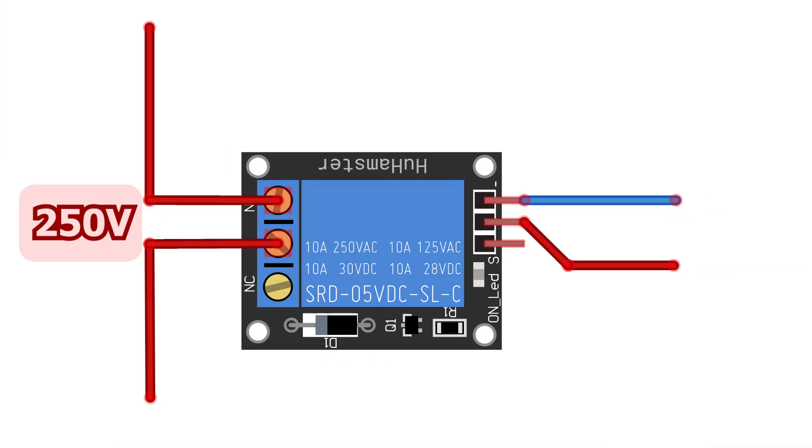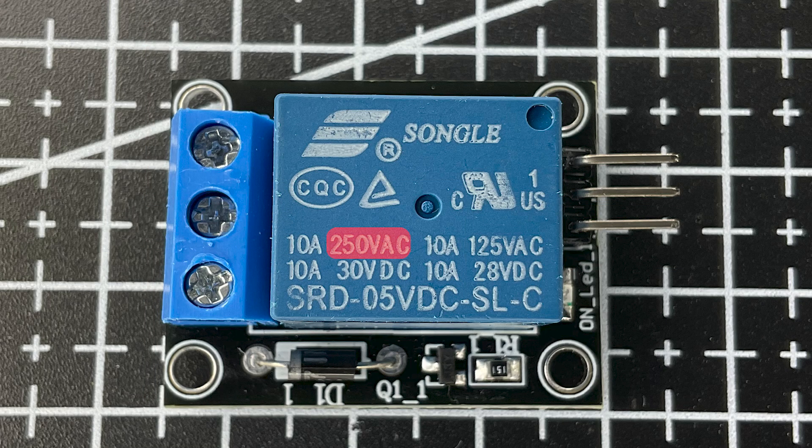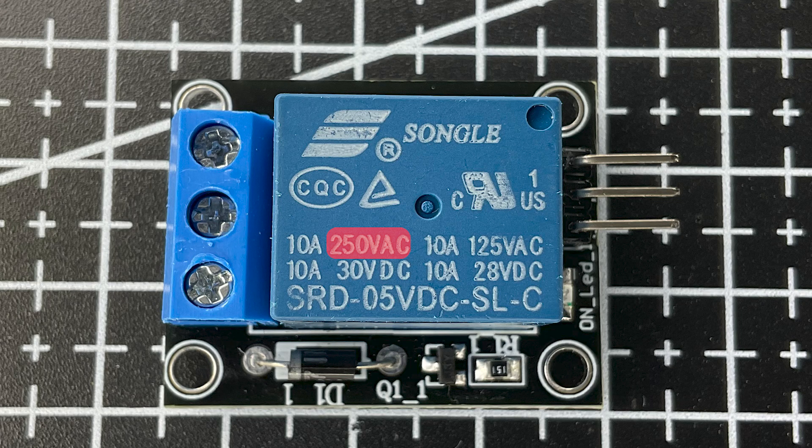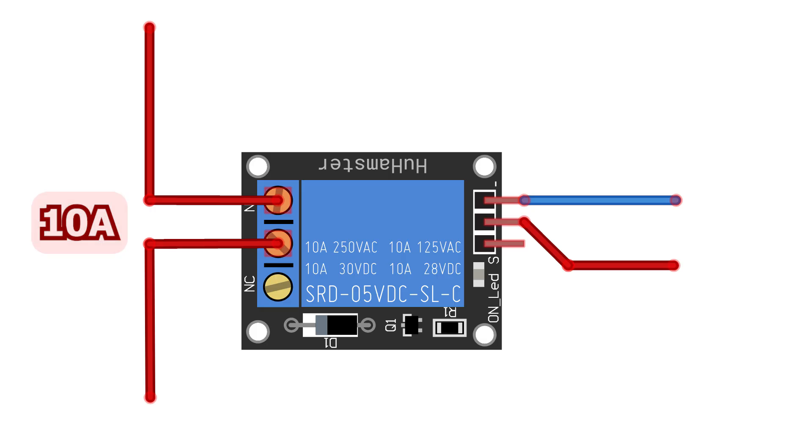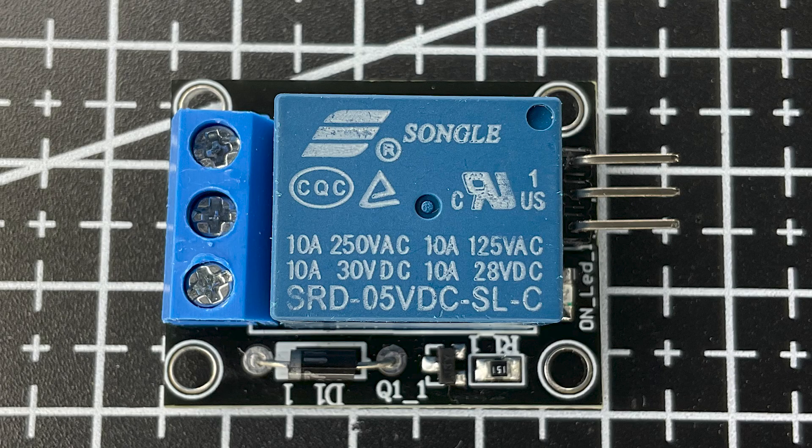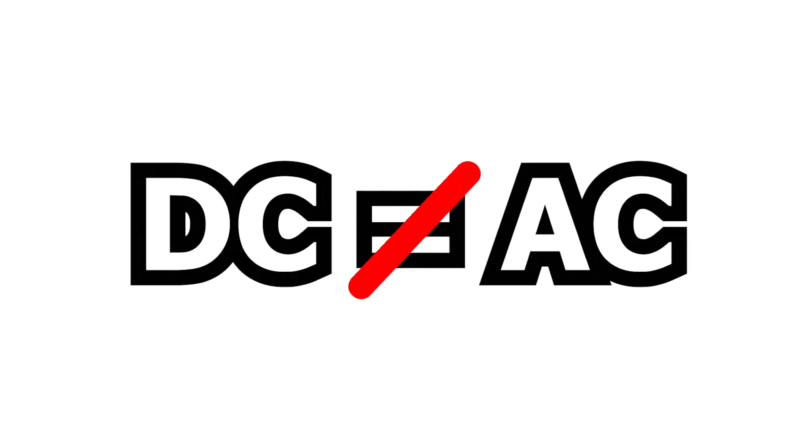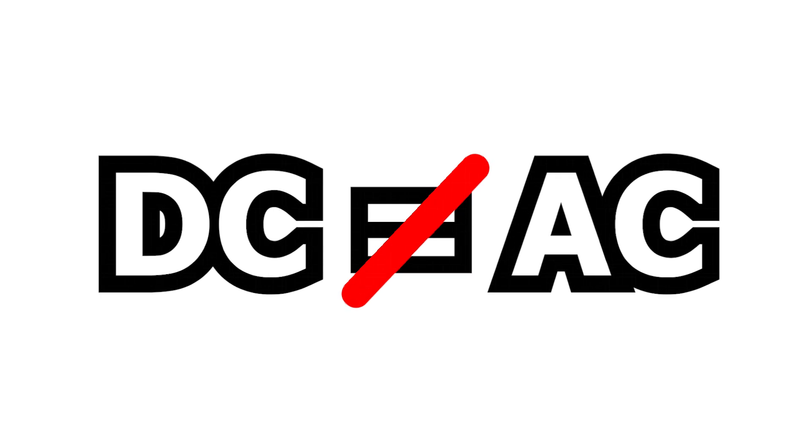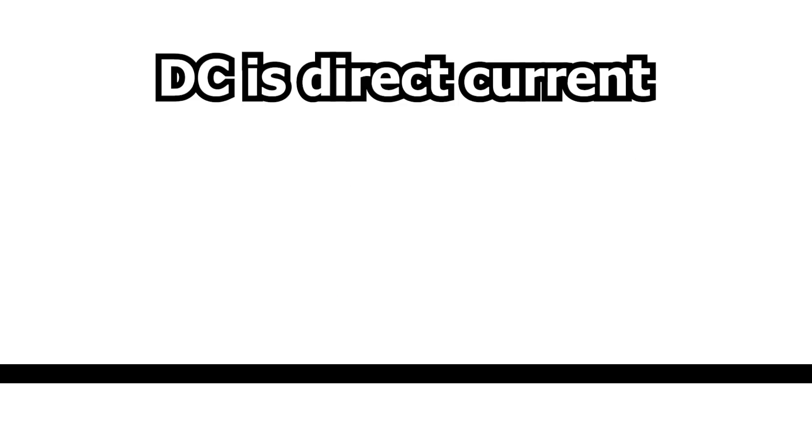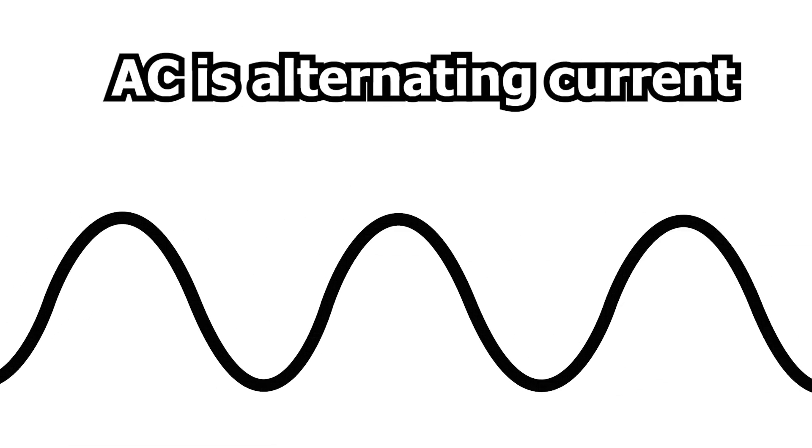Switching voltage is the maximum switching voltage, for example, 250 volts AC or 30 volts DC. Switching current is the maximum current, for example, 10 amps. It is also worth considering the type of switched current. DC is direct current and AC is alternating current.